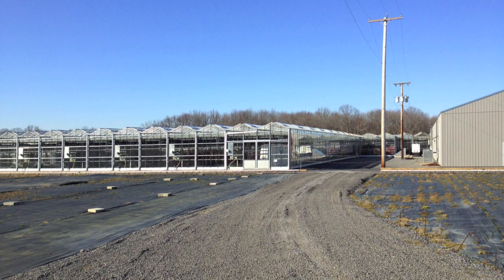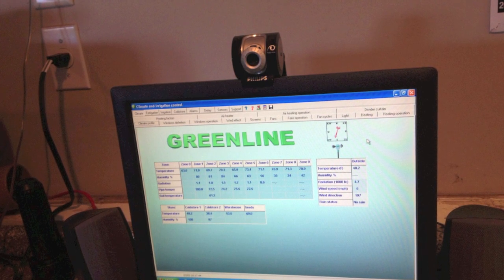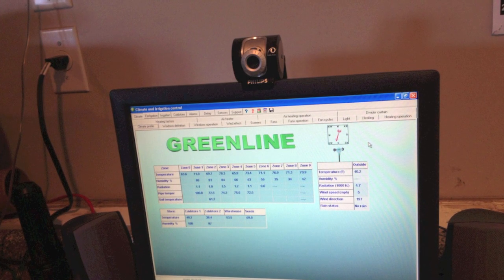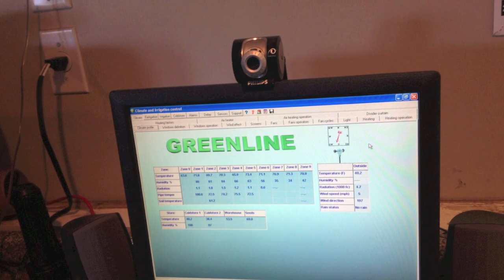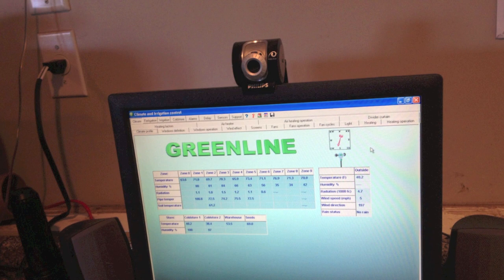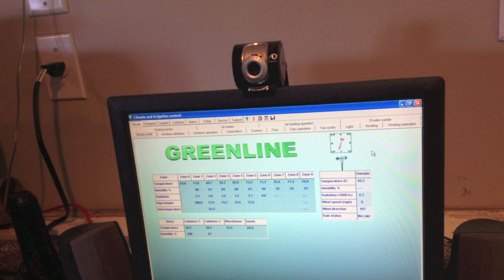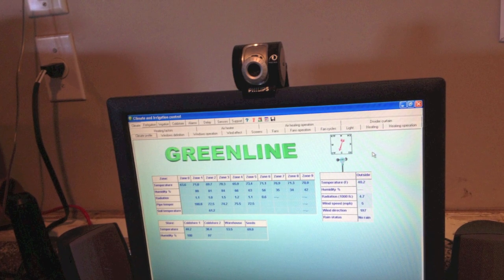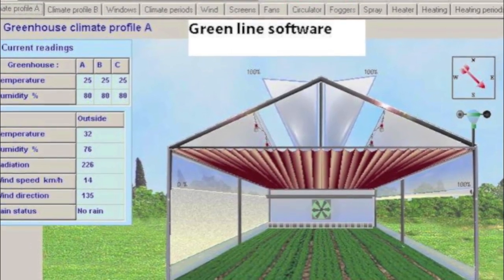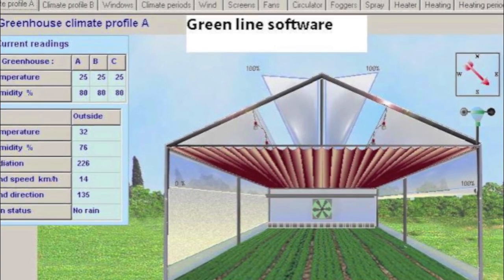The system is made of three parts. One of them is the GreenLine software. The GreenLine software is the center of everything that is going on. It displays information on the screen of what is going on in the greenhouses, including temperature, humidity, alarms and other problems. When you have a problem, you get an alarm and SMS. The system shows you what's going on in the greenhouse and outside field in a graphical interface.